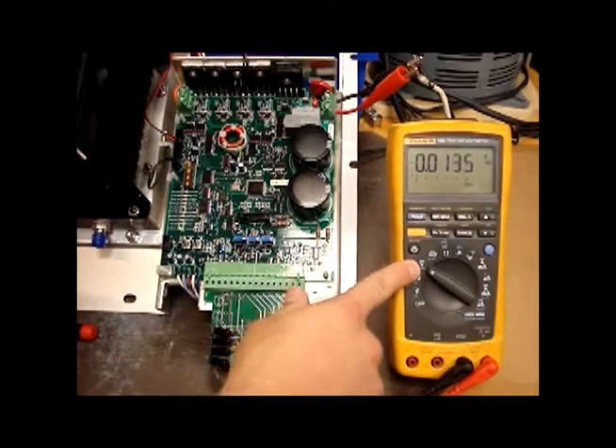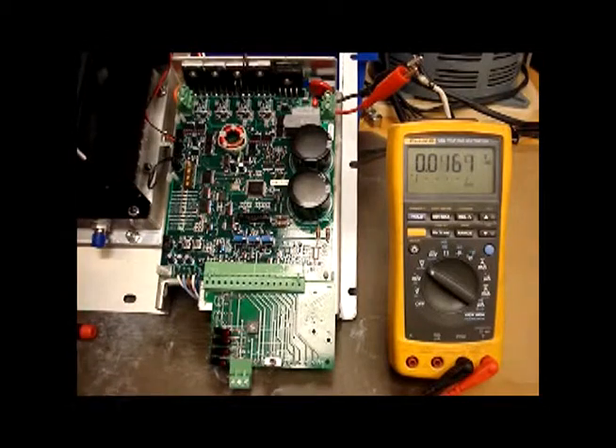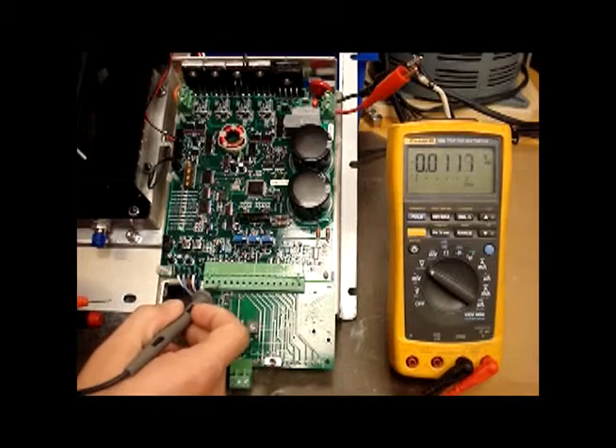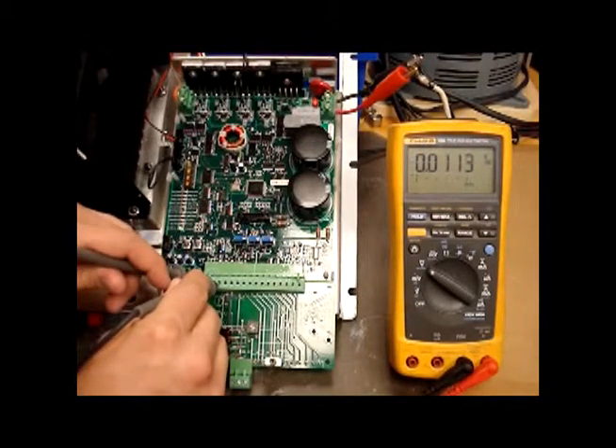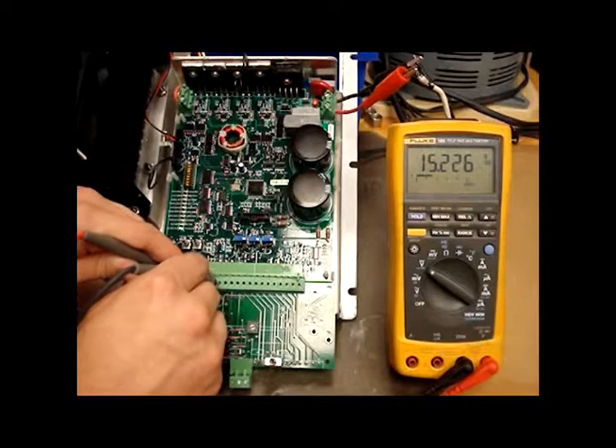We have our multimeter set at DC voltage readings, and I'll take my negative lead here on pin 3, positive lead on pin 1. Now, we should get 15 volts, and we do.